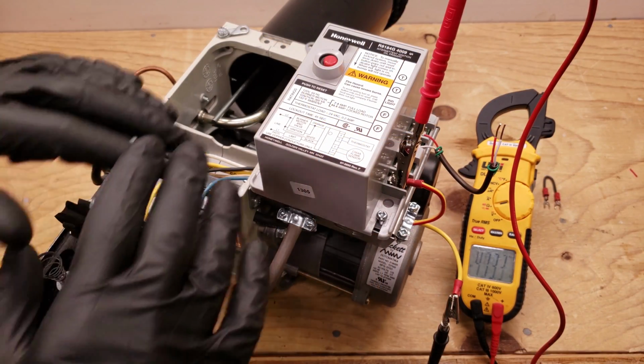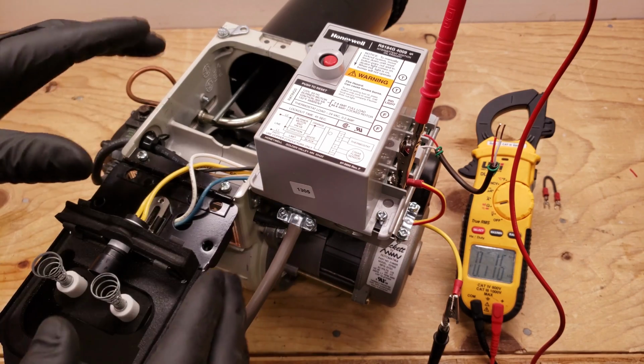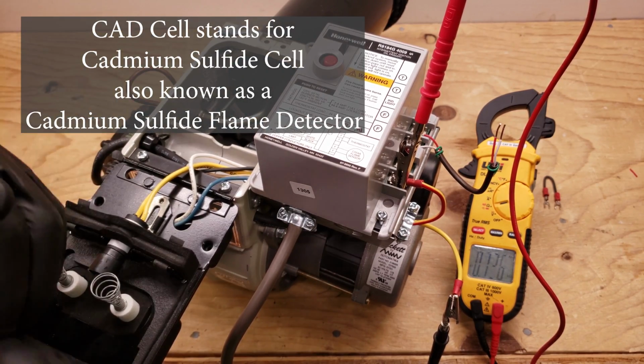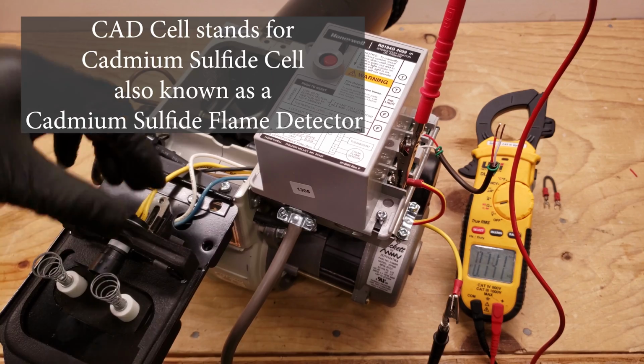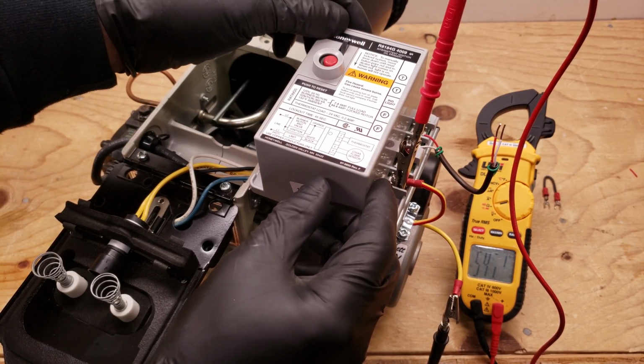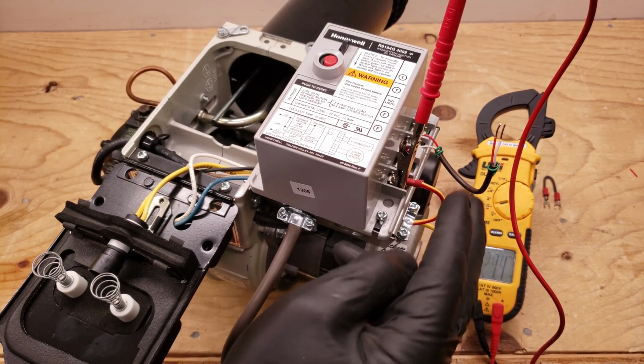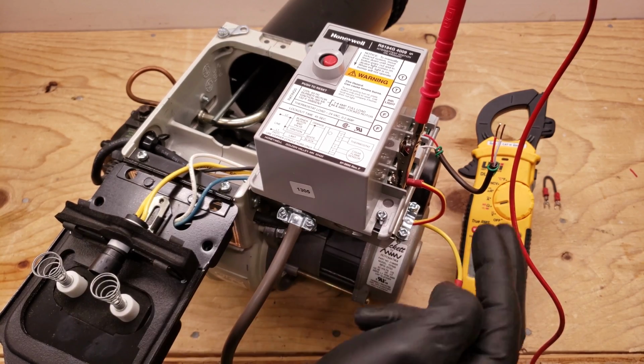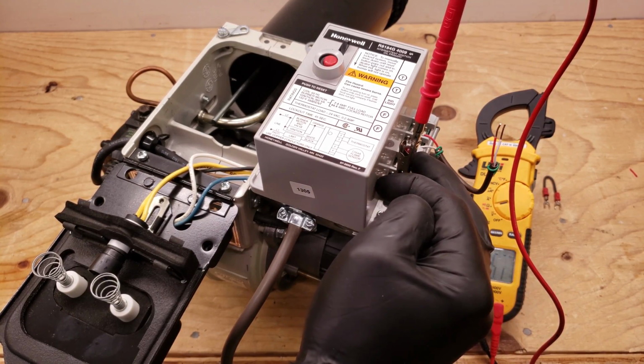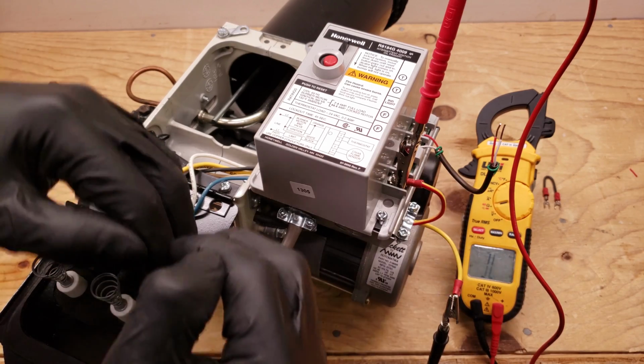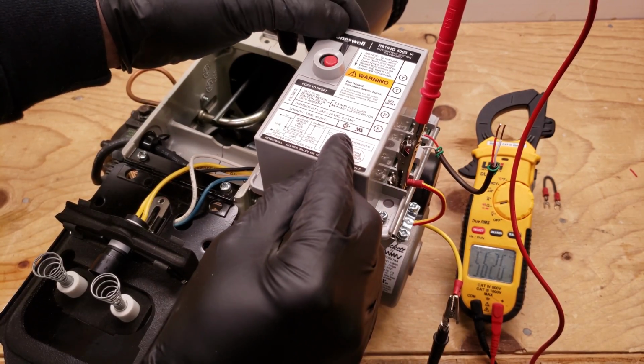Now that I briefly described the operation of the oil burner, I want to cover the CAD cell, how it works, and also the troubleshooting first. Then I'm going to cover the oil primary control. And the reason for that is that the CAD cell, these yellow wires, are getting connected into the primary control and are going to control what's happening within the oil primary control.